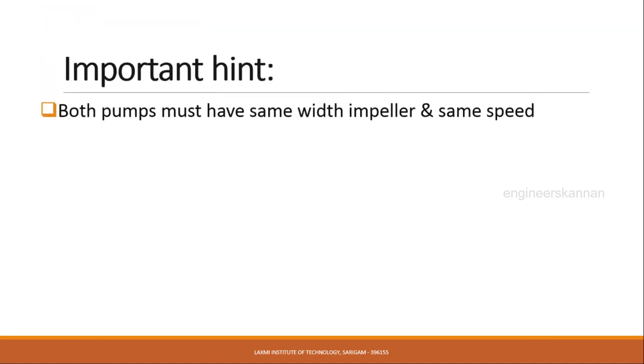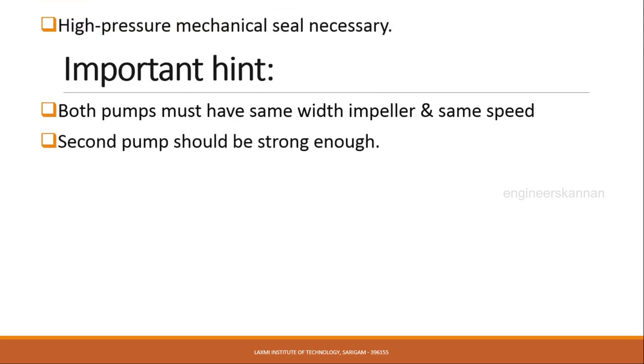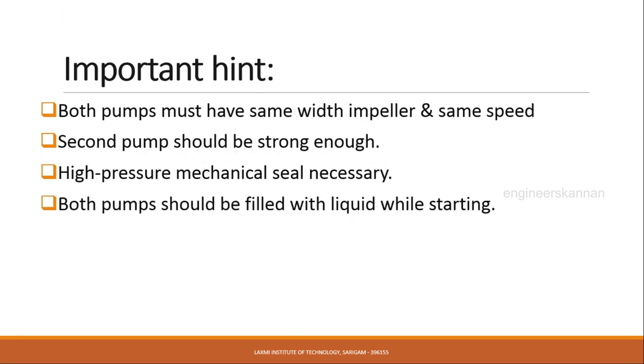There are important points to notice before connecting two pumps in series. First, both pumps must have the same width impeller and run at the same speed. The second pump must be stronger than the first, with high pressure mechanical seal compulsorily required due to pressure increment. Both pumps should be filled with liquid before starting, and always the second pump is started after the first pump.